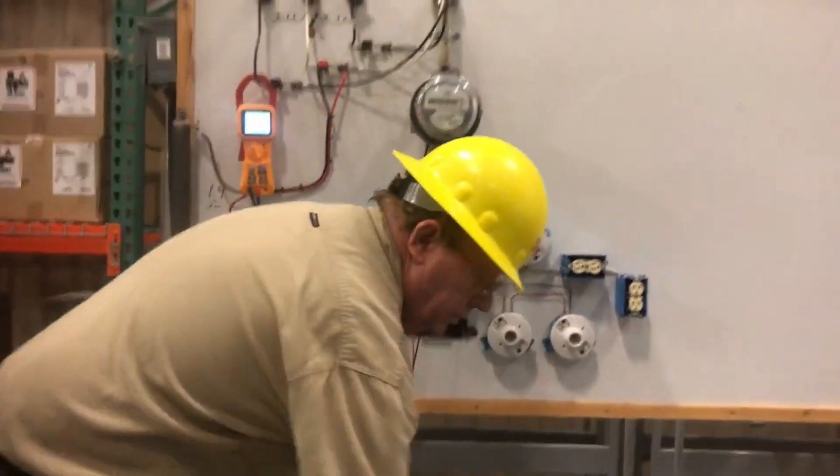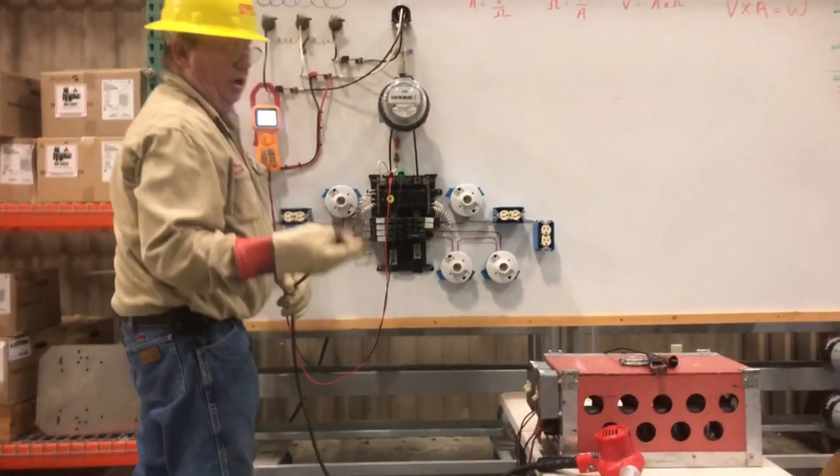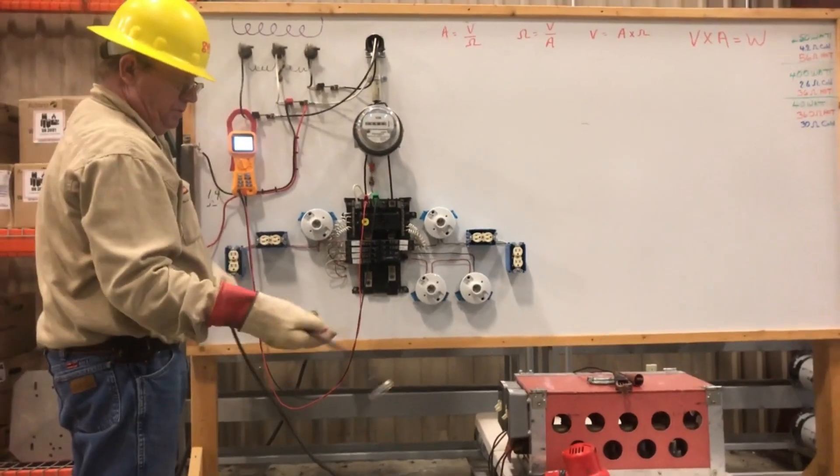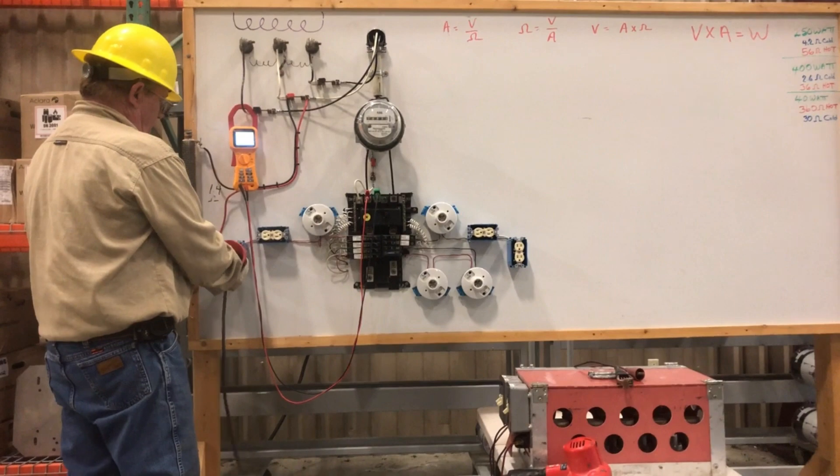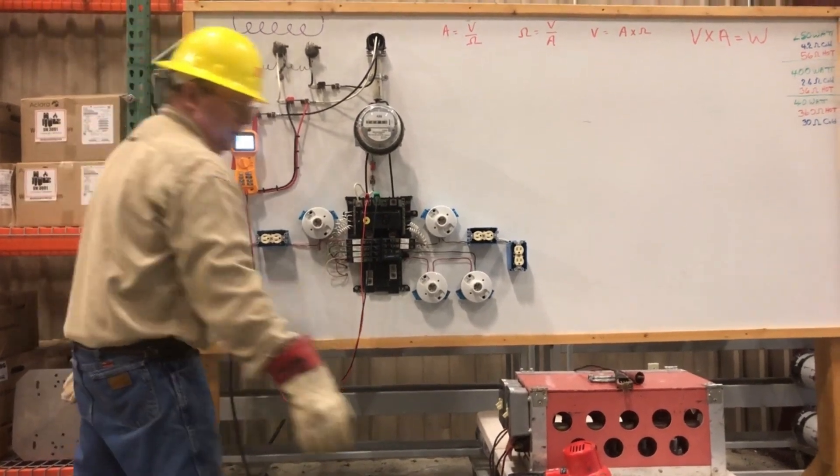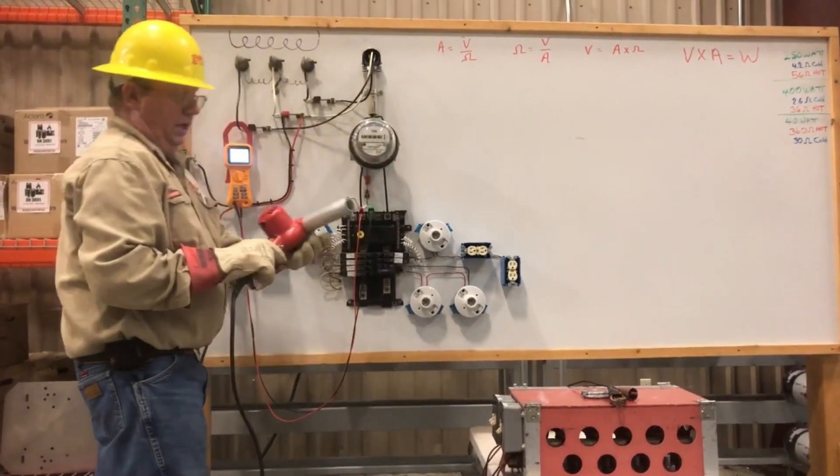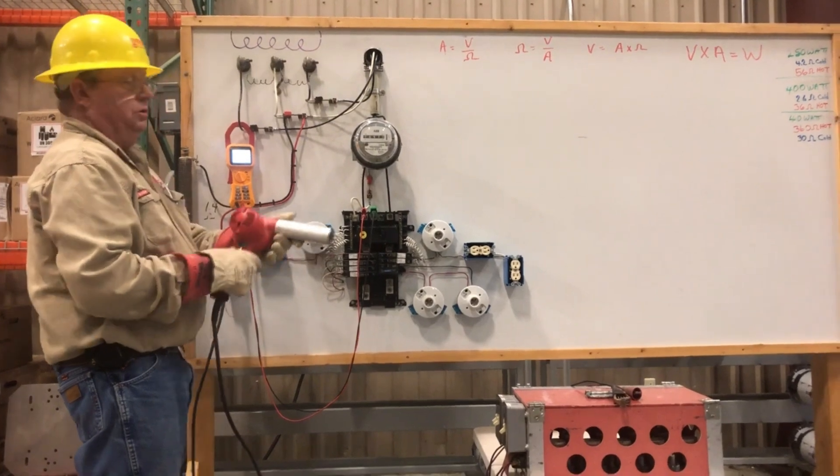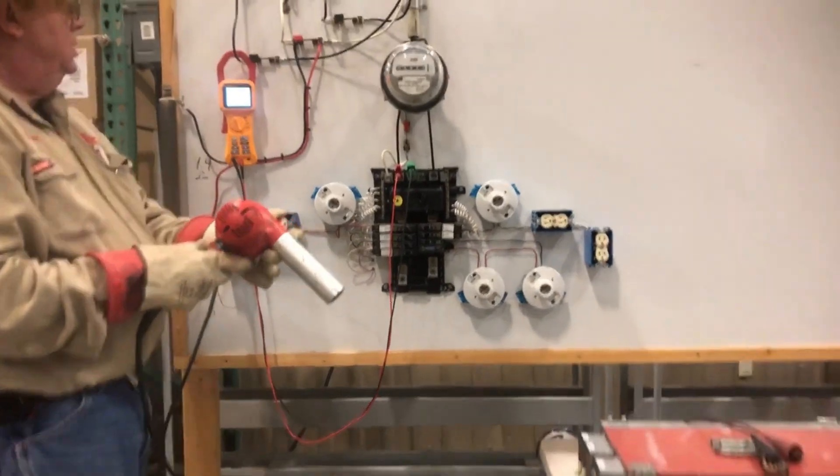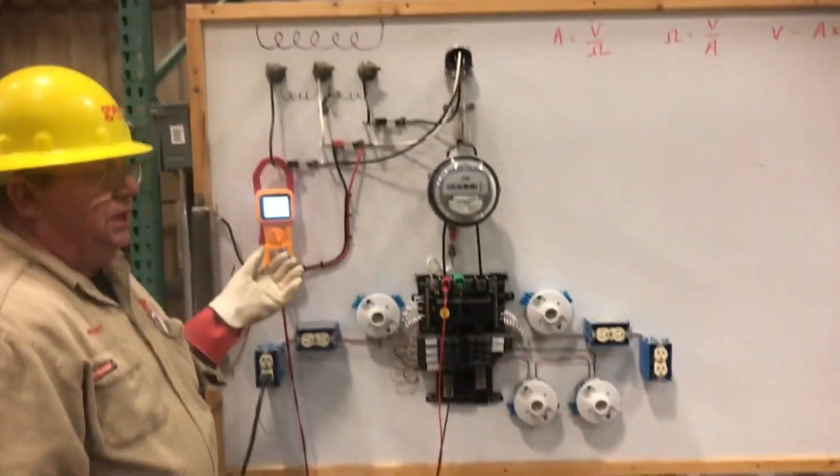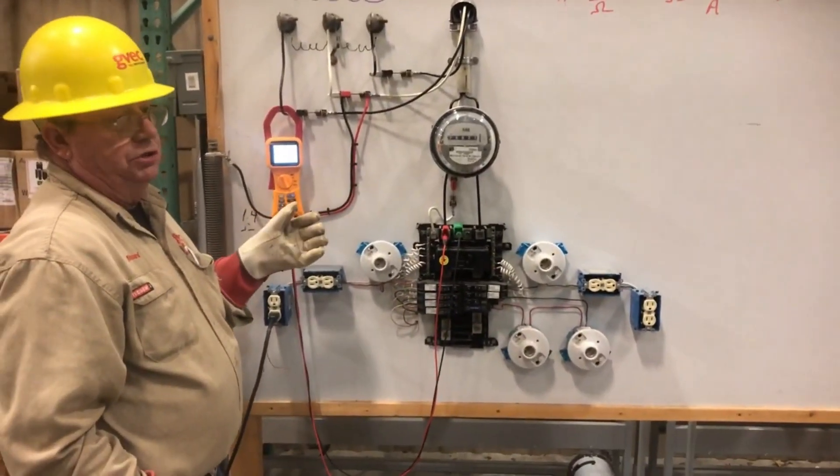Now we're going to add an external load. You're going to go and you're going to tell Ms. Smith, turn on your microwave. Ms. Smith's going to turn on her microwave, or in this case, my heat gun. And we're going to move it up to hot. 116.5 is the voltage drop.